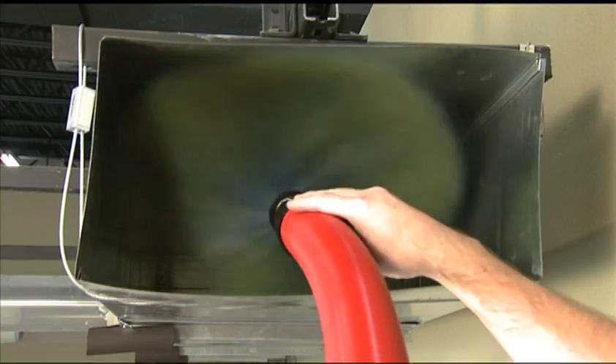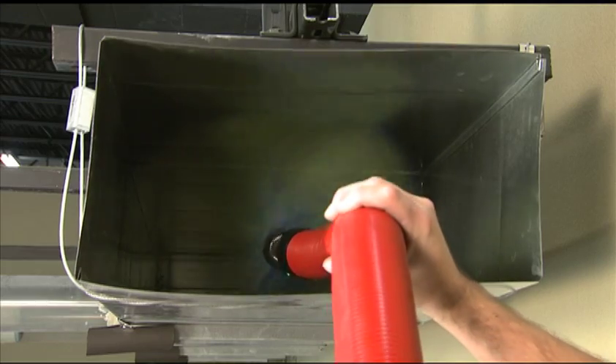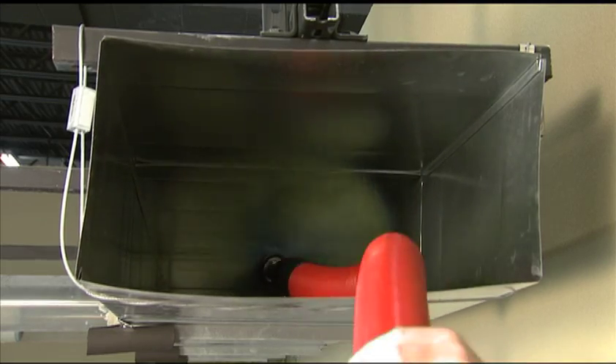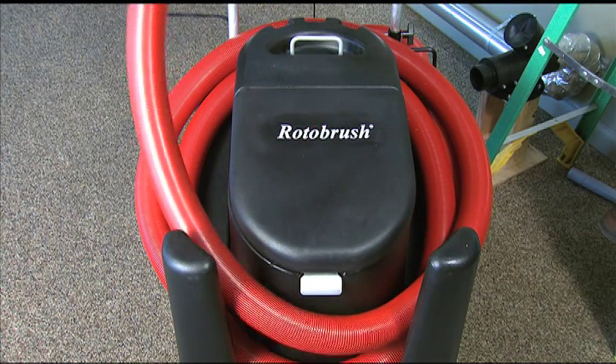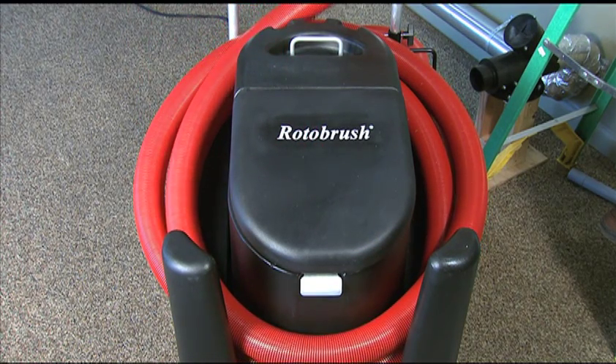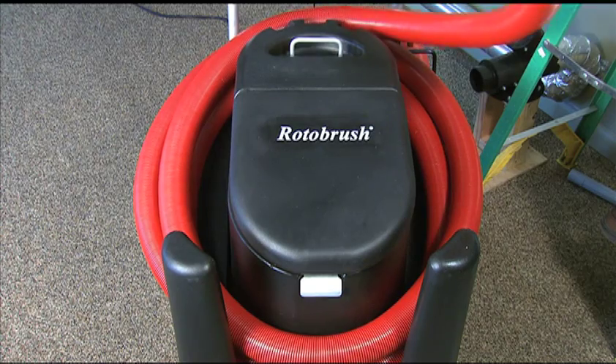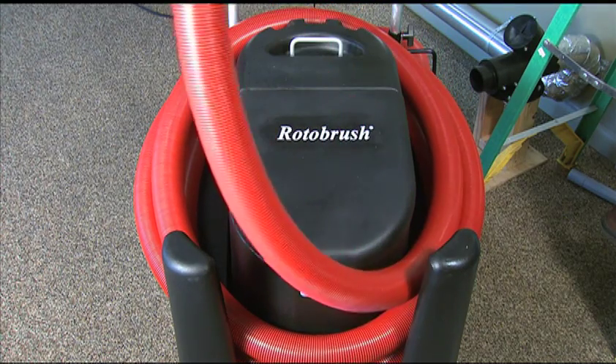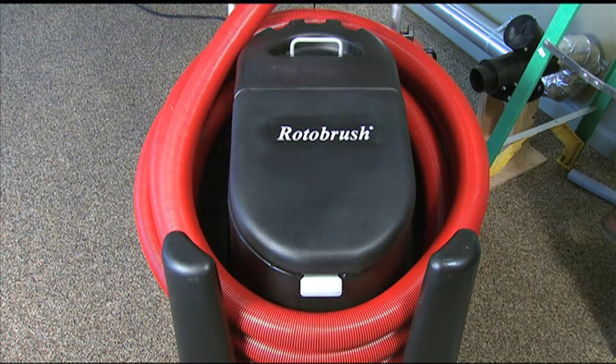Insert the brush with the vacuum on and engage the brush rotation. Again, insert the hose at a rate of about 1/2 to 1 foot per second. While removing the hose, make sure that you wrap it around the machine. This keeps the work area safe and orderly. This also prevents the hose and cable from binding, which can cause the cable to weaken or break.